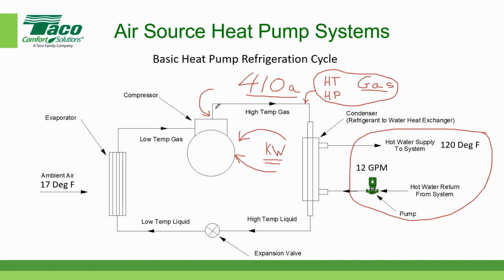So the refrigerant leaves the compressor as a high temperature, high pressure gas, and it passes through a refrigerant to water heat exchanger, also known as the condenser. And when we talk about the term condenser, we're talking about the fluid being condensed from a gas to a liquid. So when it exits this heat exchanger, it leaves here as a high temperature. You ready for this? This is really cool. It's one of the magics of refrigeration. It's still a high temperature, high pressure, but it's no longer a gas. It's now a liquid. Oh my God, isn't that cool? That'll blow your mind, won't it? LIQ. I'm blown away already.